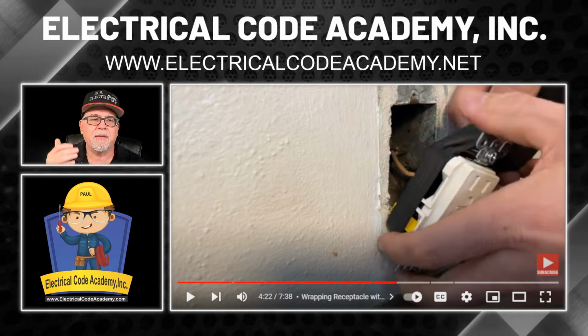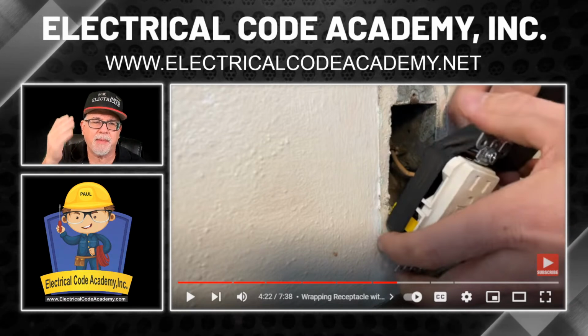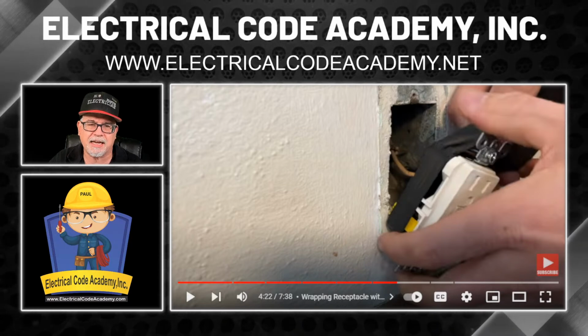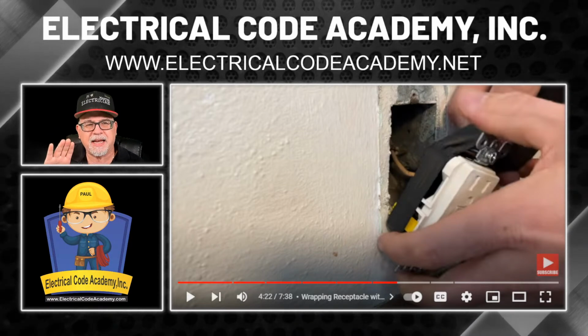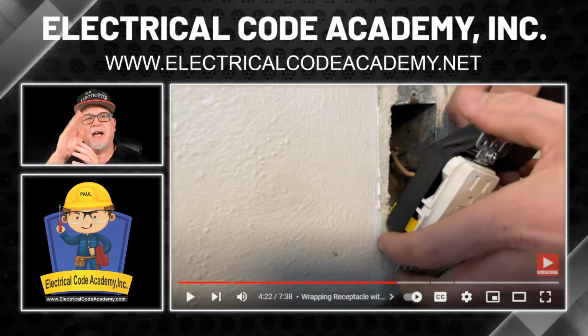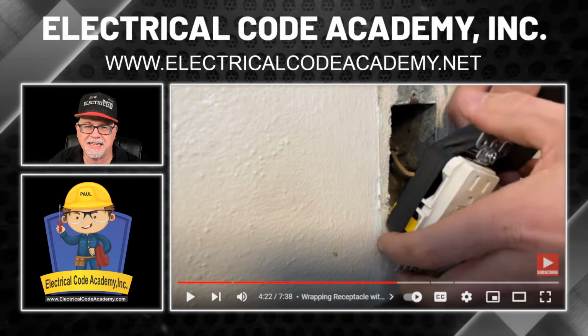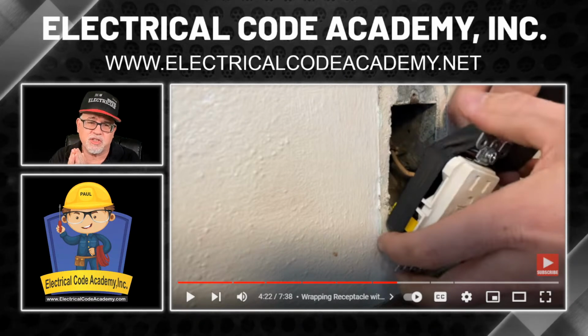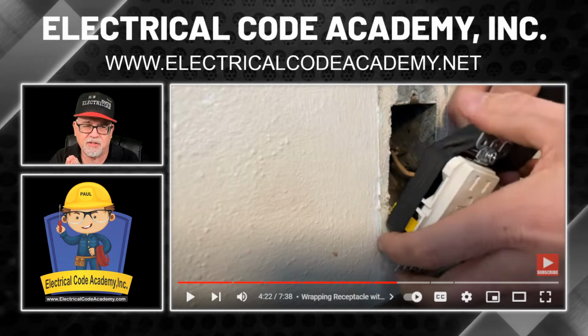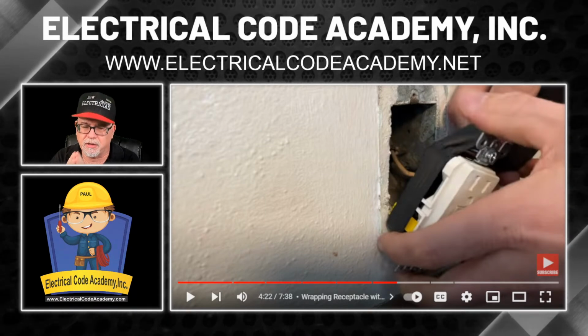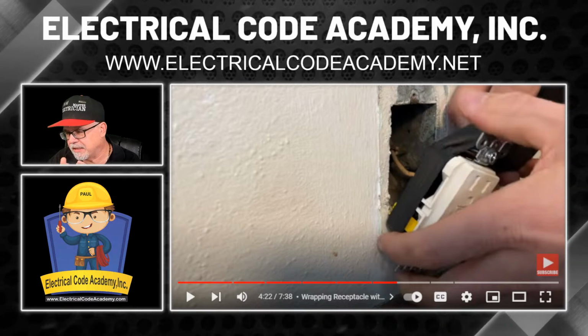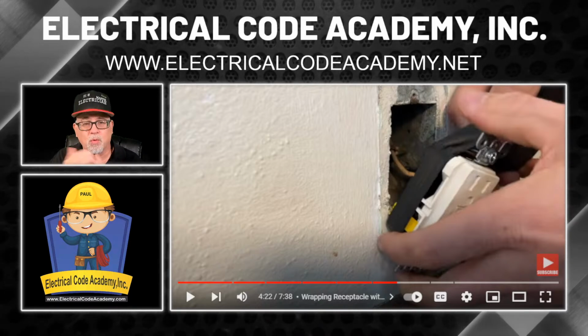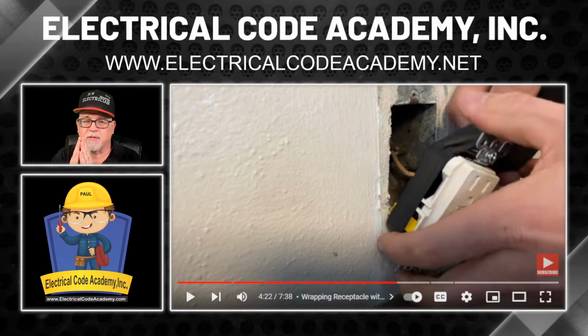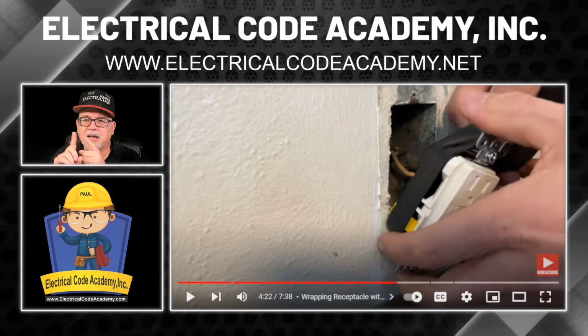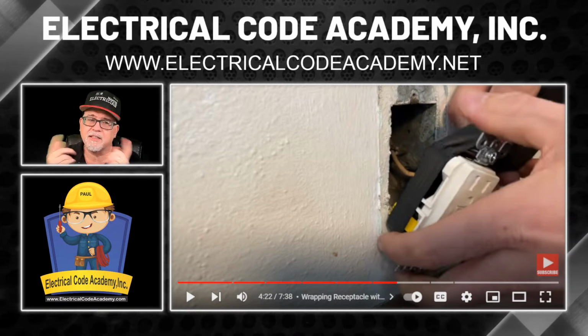It ultimately ended up the problem was the old insulation, brittle, cracking off as you're pushing that device back in there, and it ends up bending and touching the side of the metal or something like that. So I always worked very gingerly around the old insulation because it was probably old and brittle. If you start moving it around a lot, it will crack. And if it cracks at the fulcrum where you're bending it, the black and the white could touch and you get a dead short.